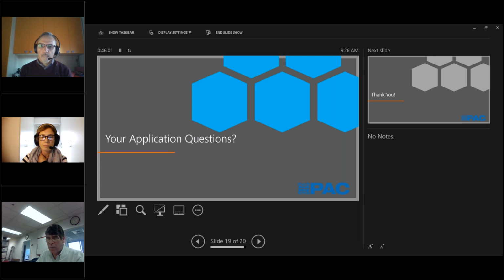So let's say, as an example, you got a 1-to-20 piston, but you find out in the future that you need to measure a thicker fluid. Using that web user interface would allow you to calibrate a new piston to the viscometer using new calibration fluids to increase your measurement range. Right, and those calibration menus are accessible in the user interface, and there are instructions in the manual for how to do a full factory calibration as we do it here, which is multi-point calibration, or there's another type of calibration in there, right?